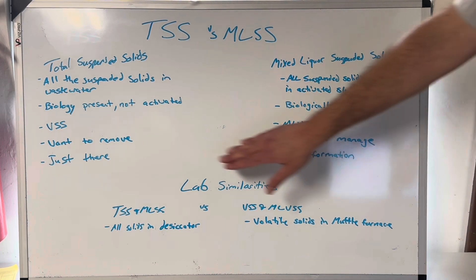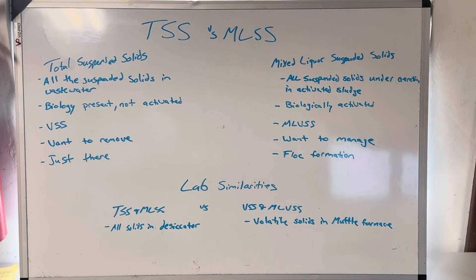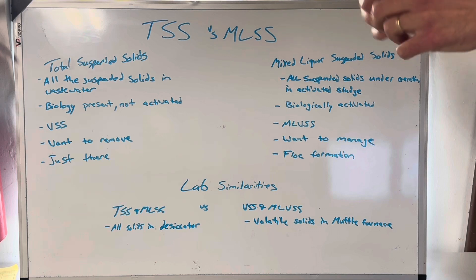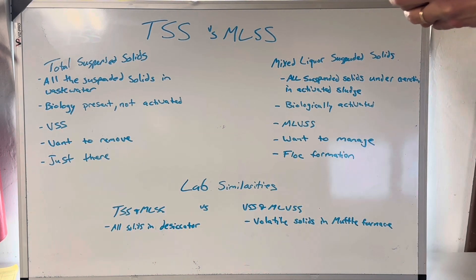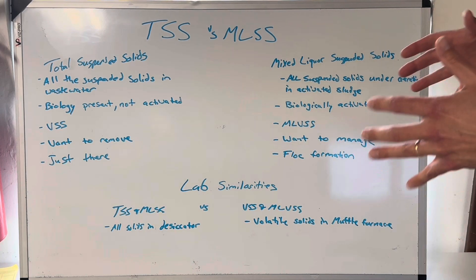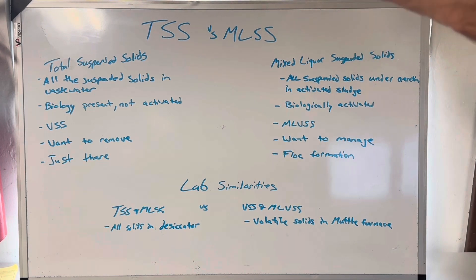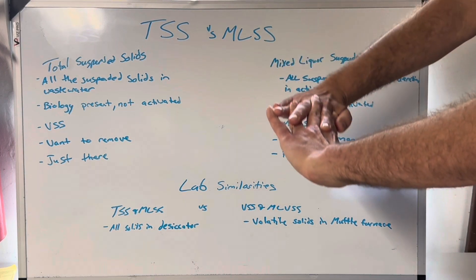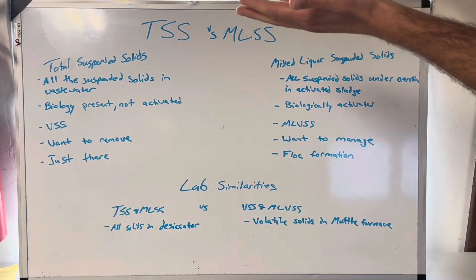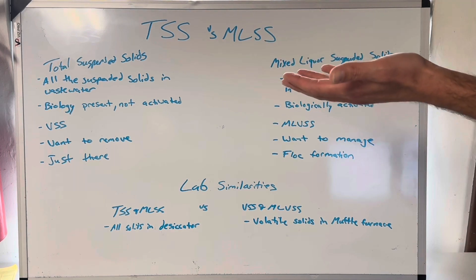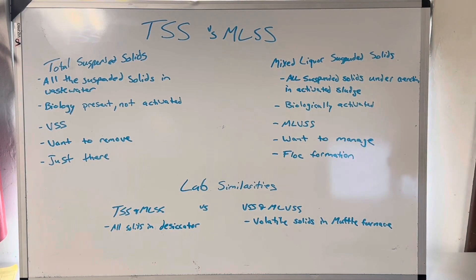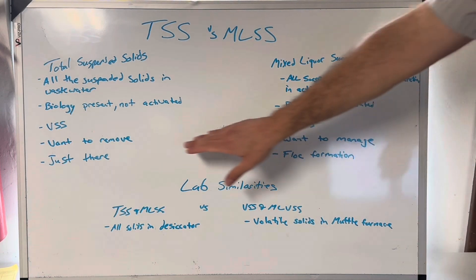You want to manage MLSS — this is a harnessed biology. Think about floc formation versus just being there. Floc is the best — think of static cling in your dryer where your clothes came out all static and they're sticking to you. That's a great example of floc; it gathers to itself. When the mixed liquor goes into the clarifier, it forms this floc and creates kind of a metaphorical net that pulls everything down to the bottom of the clarifier. What's left on top is clear water — supernatant — that goes on to the next process. You might have some scum layer on top, which is fairly normal.